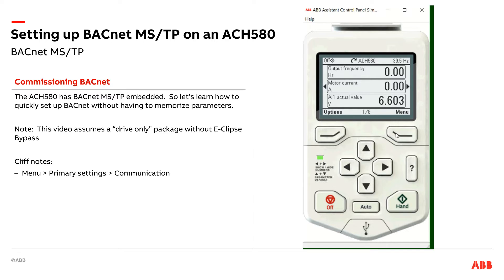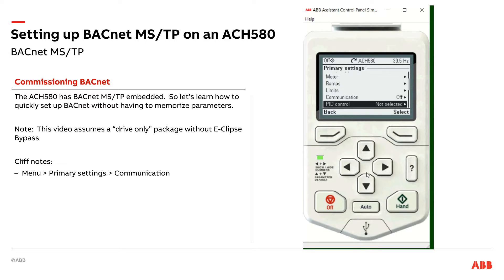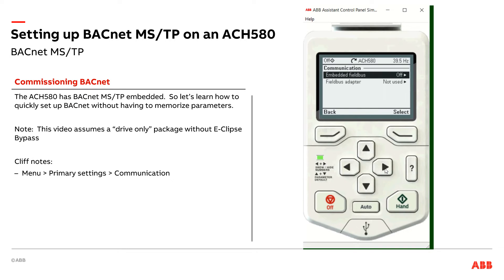The first thing I'm going to do is hit Menu and go into Primary Settings. For all you controls contractors out there who do a little bit with ABB drives but not a whole lot, don't worry about memorizing parameters. Just remember these basic steps: Primary Settings, then scroll down to Communication — it's right here on the main tree — hit Select, and go into the Communication Setup and EFB, which stands for Embedded Fieldbus.